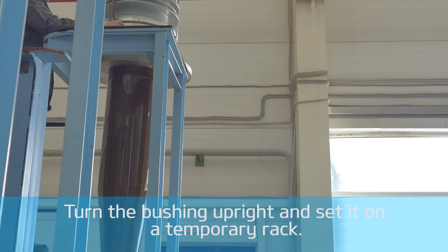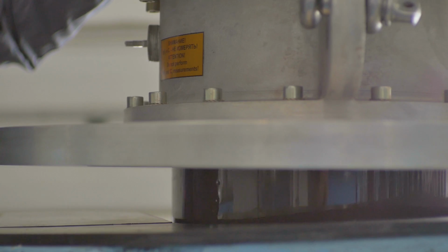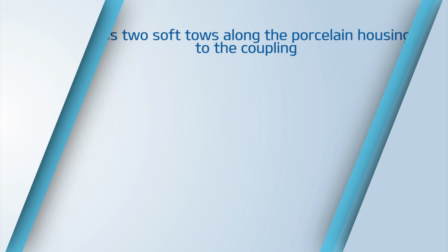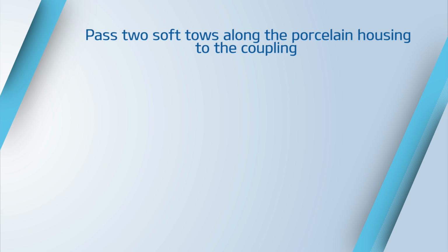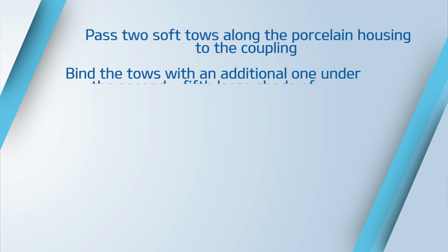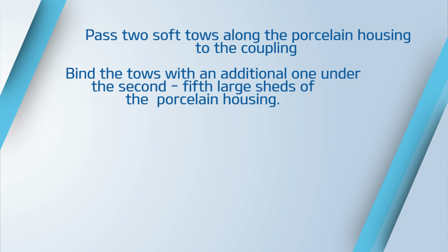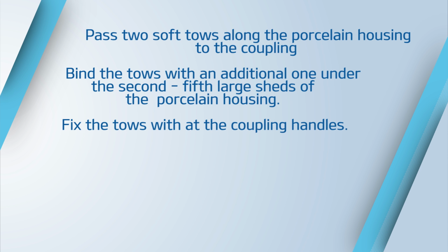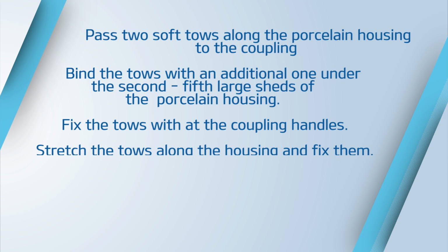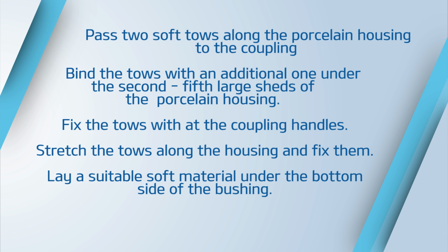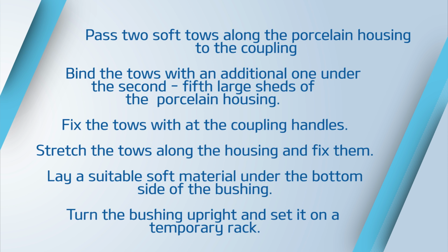We have talked about setting of the bushing to a vertical position on a stand. Now let's go through the key points again. Pass 2 soft tows along the porcelain housing to the coupling. Bind the tows with an additional one under the second, 5th large sheds of the porcelain housing. Fix the tows at the coupling handles. Stretch the tows along the housing and fix them. Place a suitable soft material under the bottom side of the bushing. Turn the bushing upright and set it on a temporary rack.